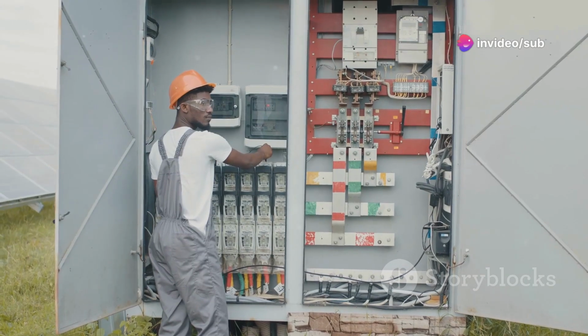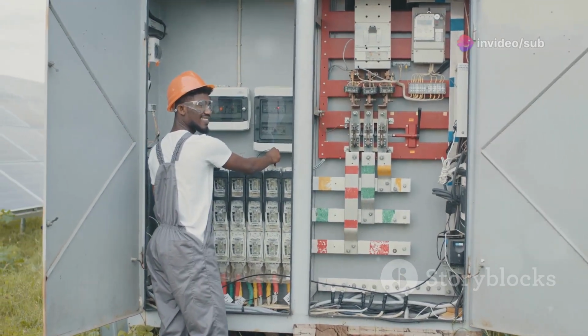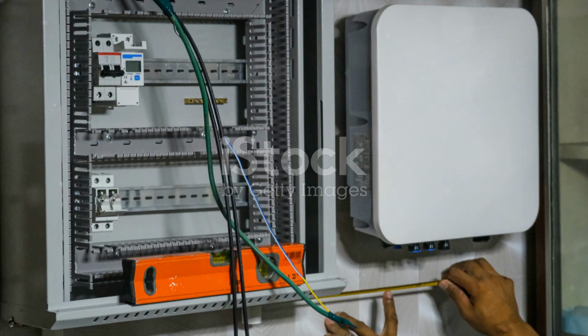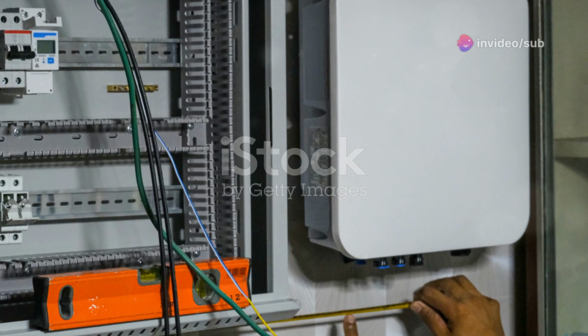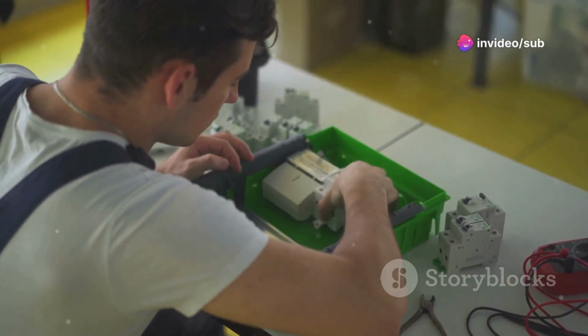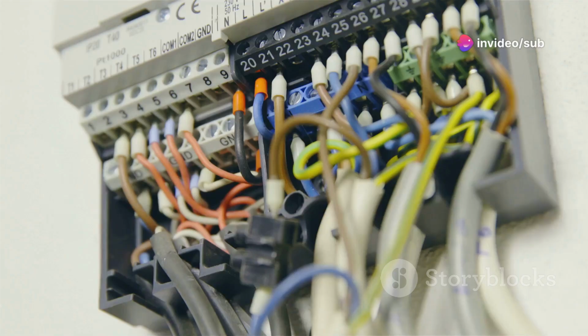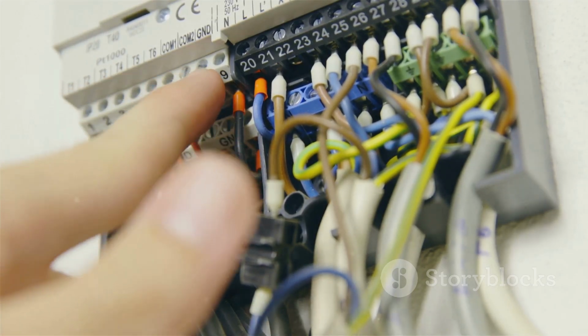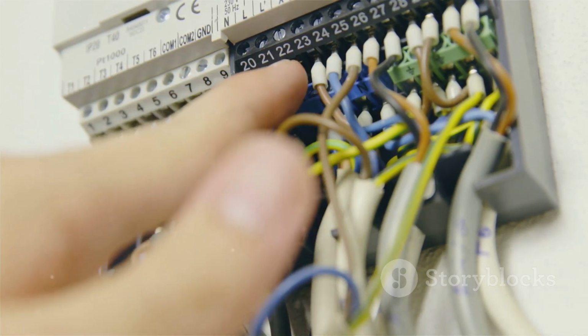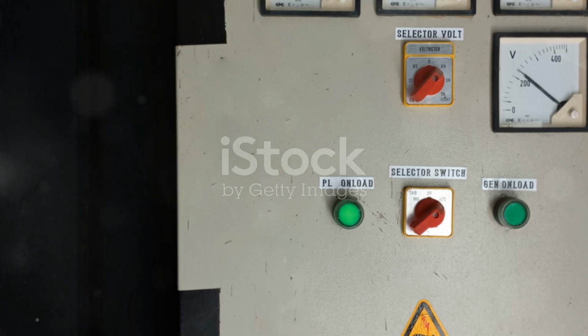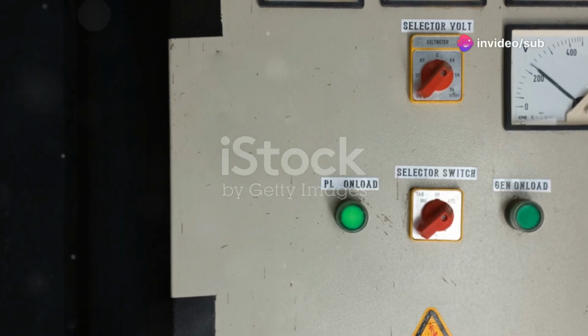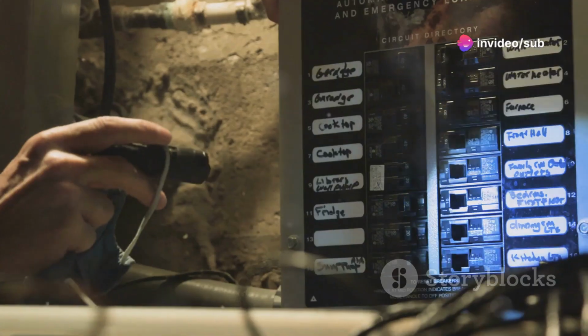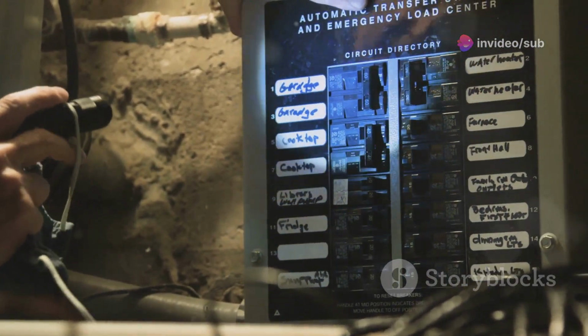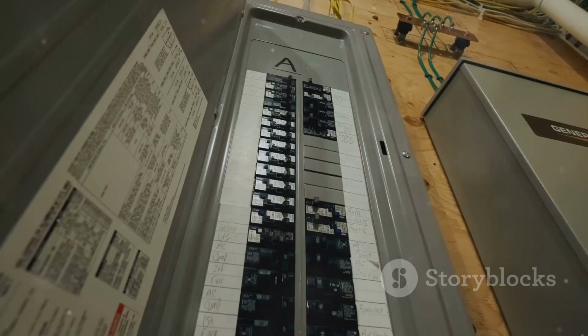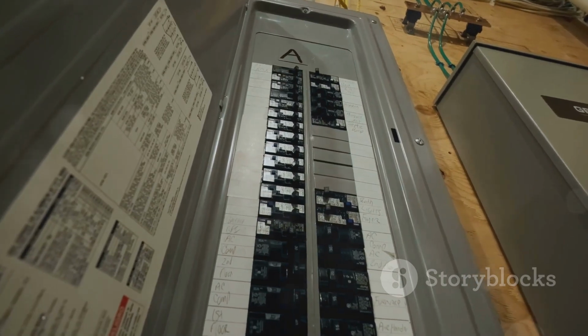The automatic transfer switch, or ATS, lets your system switch from grid to battery power during outages. Mount the ATS close to your main panel and inverter, and use screws or brackets for a solid fit. Connect the ATS to the inverter, the grid, and the panel that supplies your essential loads. Make sure to use wires rated for the proper voltage and current, and label all connections clearly to avoid mistakes. When wiring, always follow the diagram from the ATS manufacturer. It's really important to make sure essential circuits, like lights, your fridge, and outlets, are connected to the backup side. This ensures only important loads use battery power during outages.